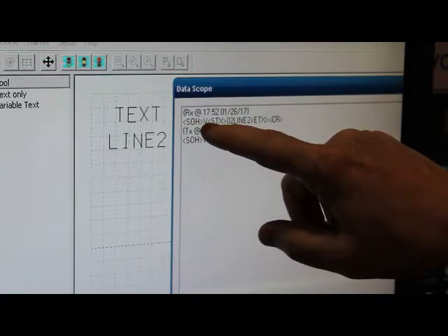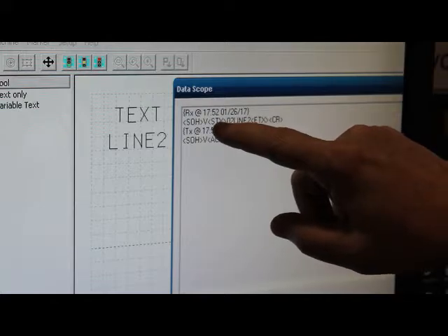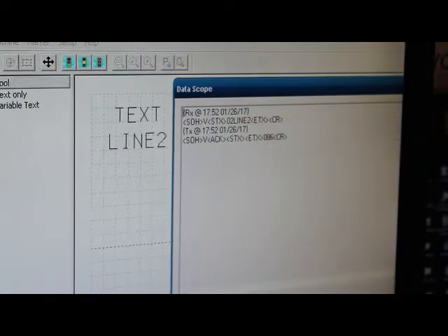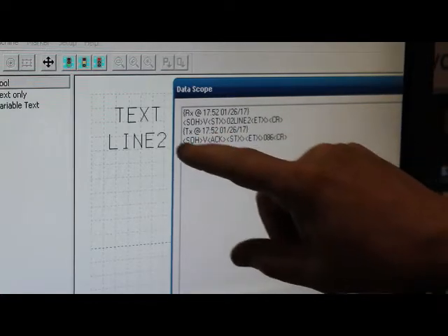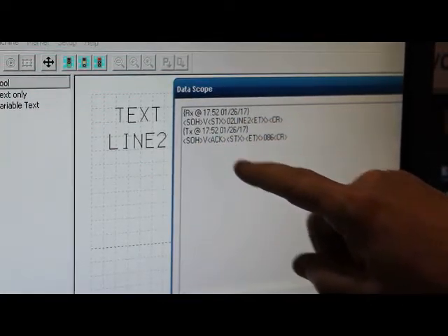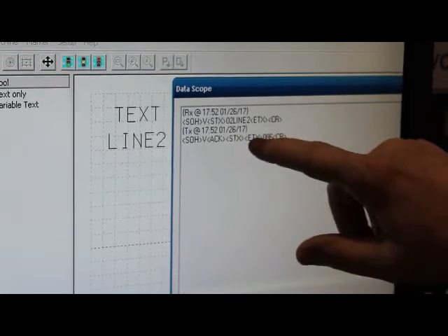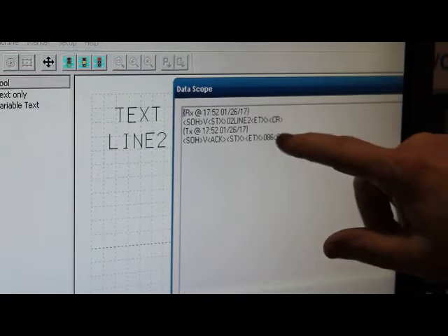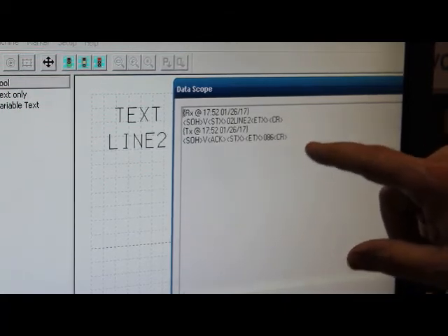These show up like this because, in this case, it's ASCII number 1, ASCII number 2, and those are non-printable characters, so it just shows the start of header as a representation of that. Then it tells me that it's sent back at the same time: start of header, the variable, acknowledge, which means yes, we did receive it okay, start of text and end of text, it's not really sending any text back, the ASCII equivalent of this V, and the carriage return, which is the terminator.